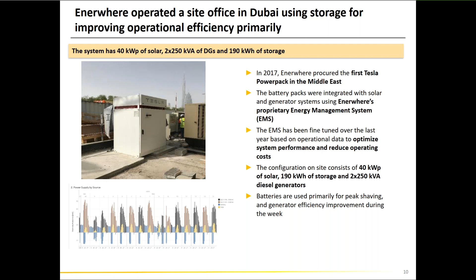The battery serves two or three specific applications. Here's real data from an operating site: diesel generators operate better with a flat load, loaded optimally for best efficiency. One application we use the batteries for is peak shaving, similar to an application Amit mentioned earlier for the grid, ensuring a flat load on the generators and improving site efficiency.